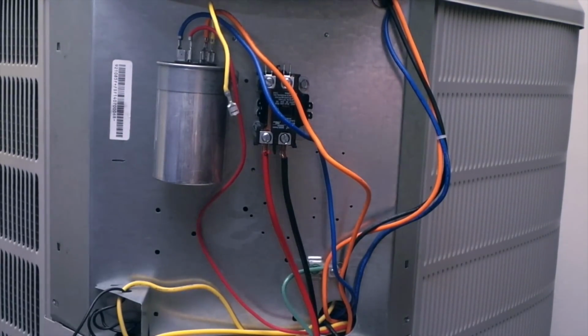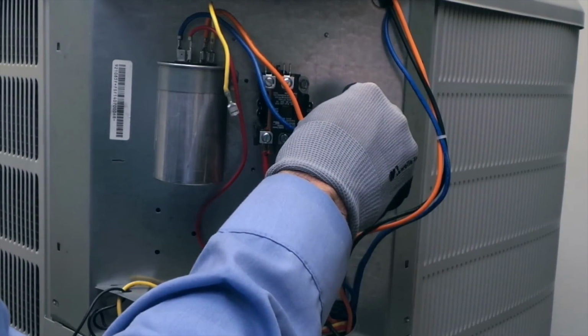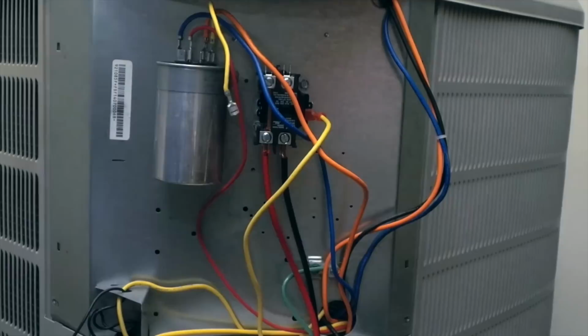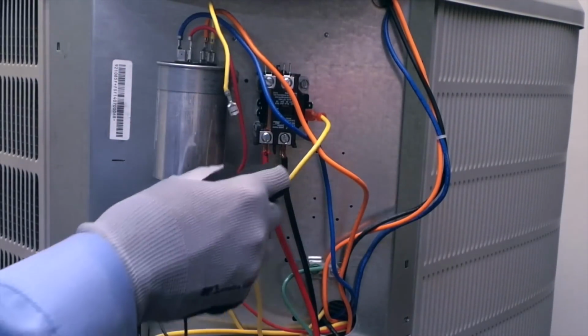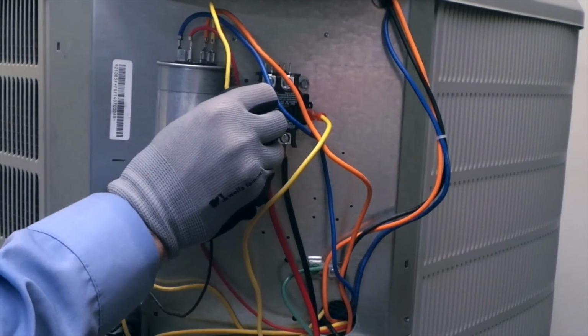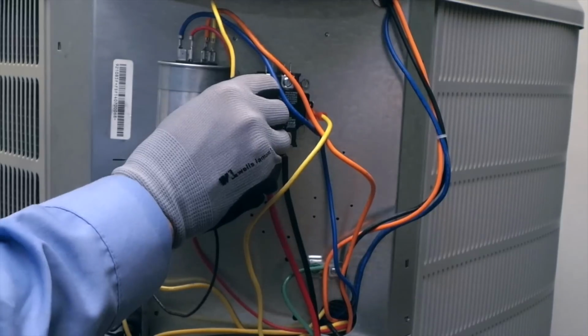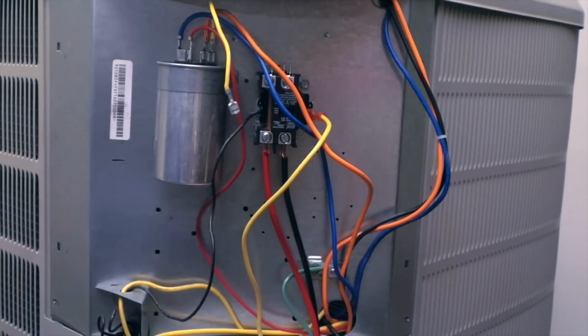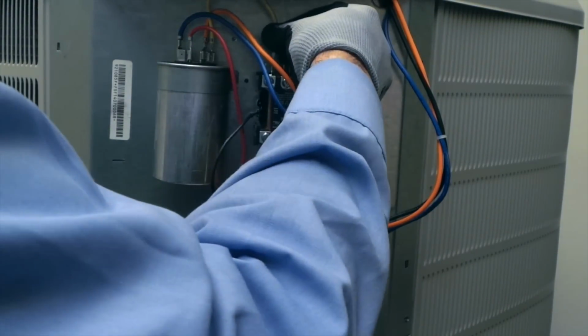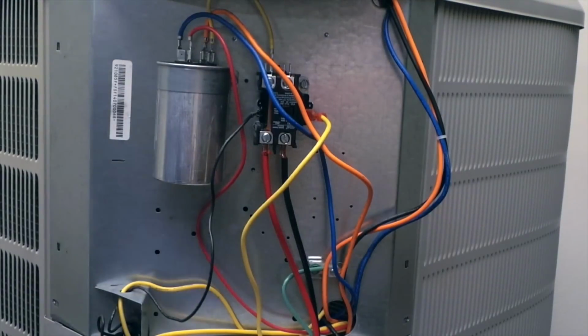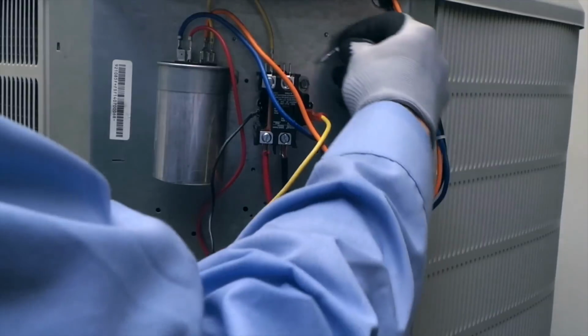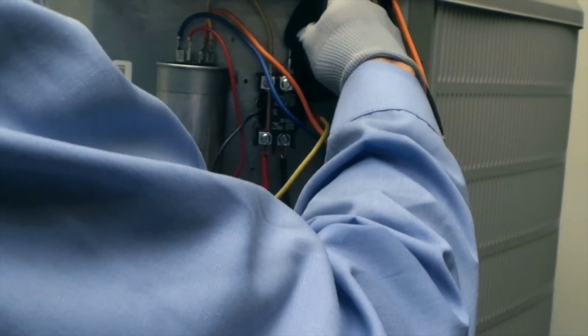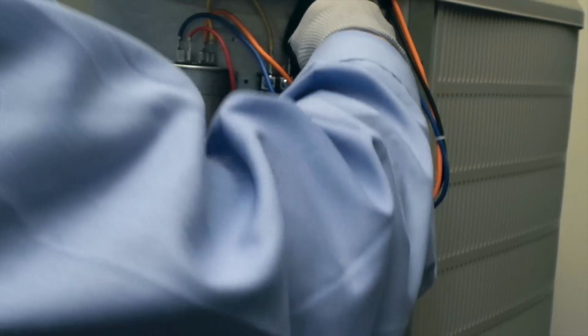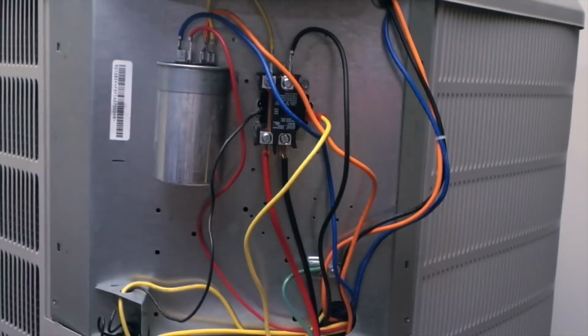Now let's hook the low voltage wires to the coil of our contactor. There are terminals located one on each side of the contactor. Now let's hook up the load side of our contactor. The common wire from the capacitor goes on the left, and our line voltage wire from our outdoor fan motor goes on the right, making sure that these are connected tightly and secure.